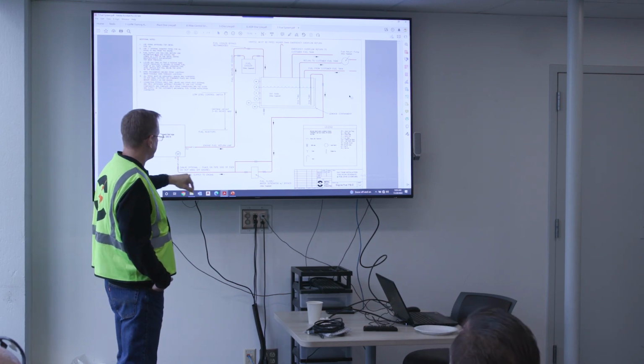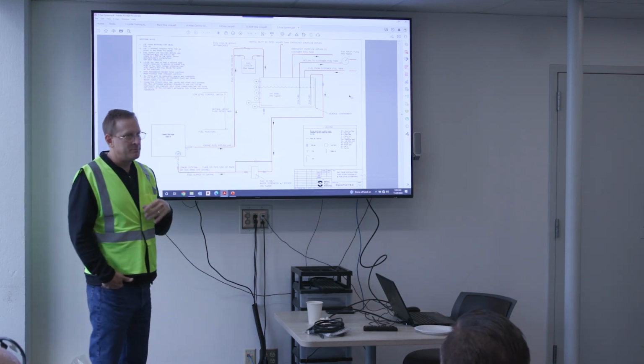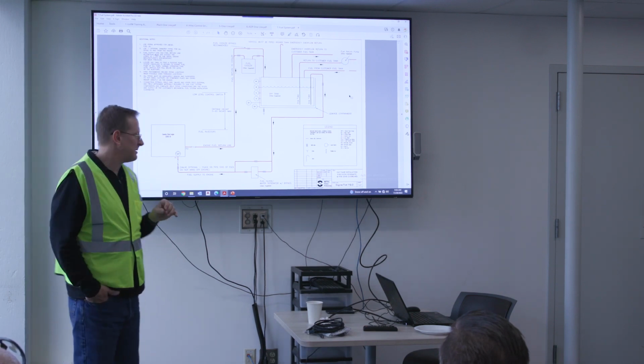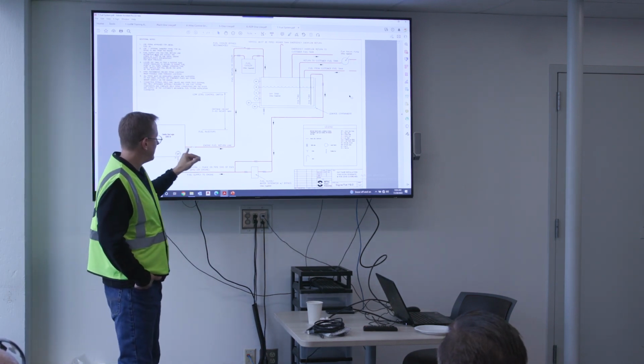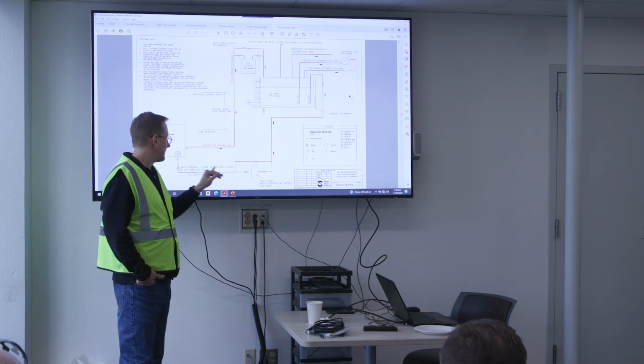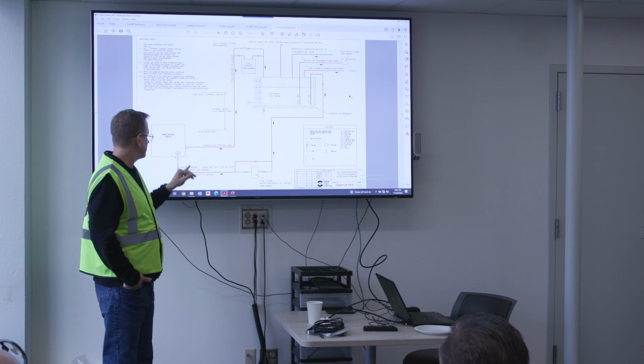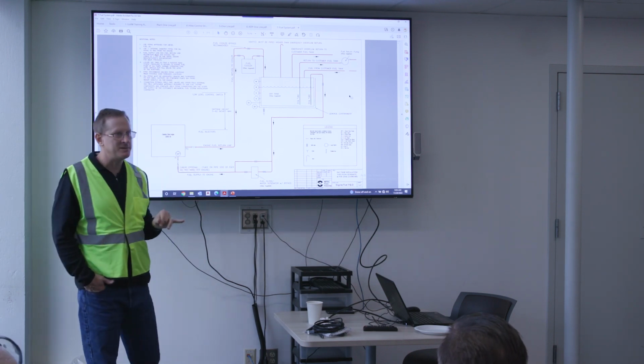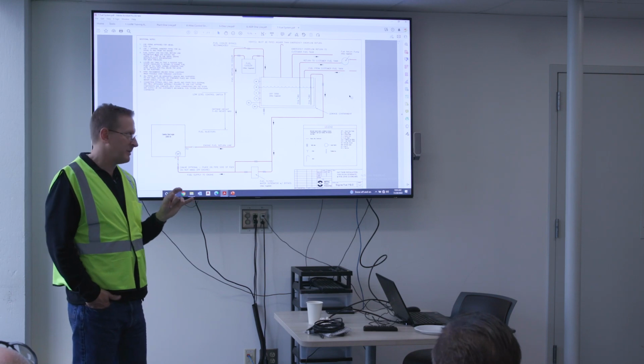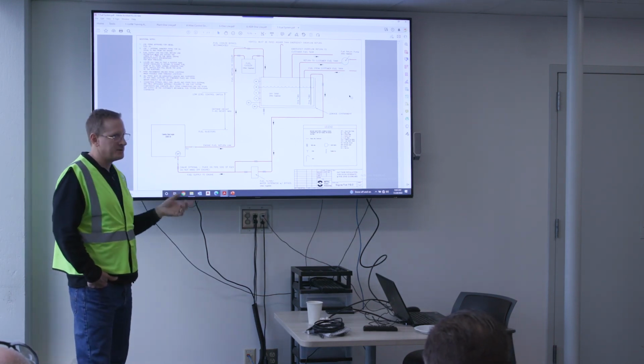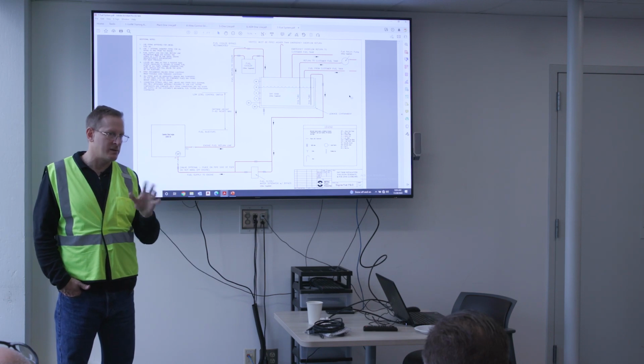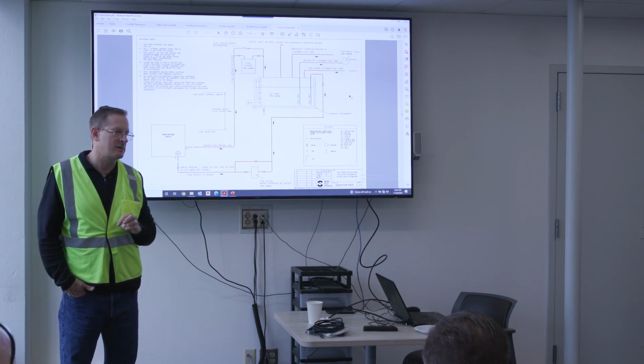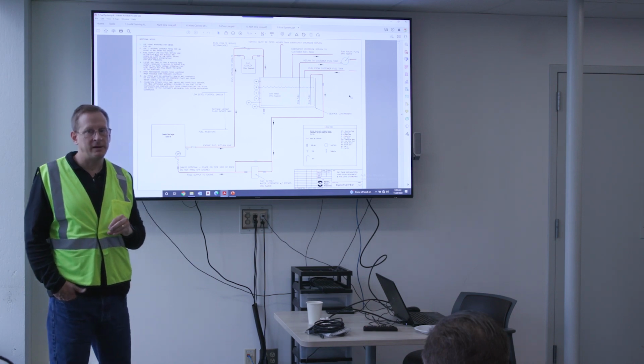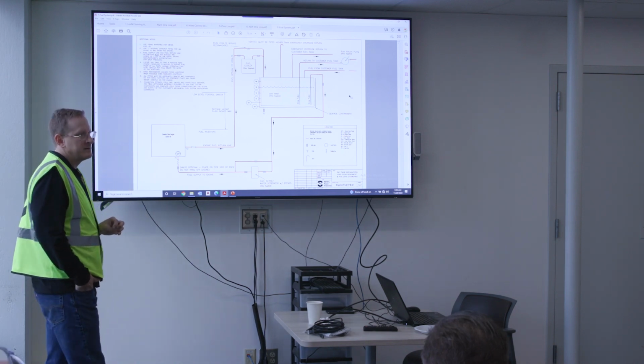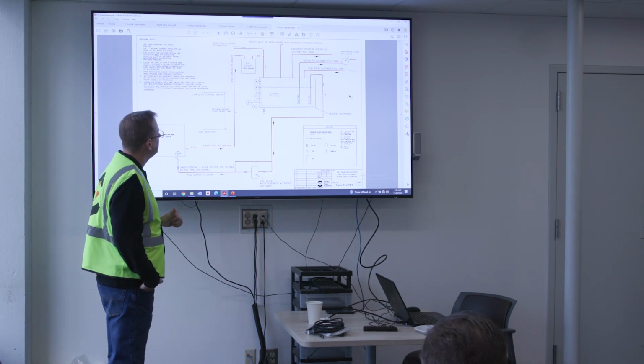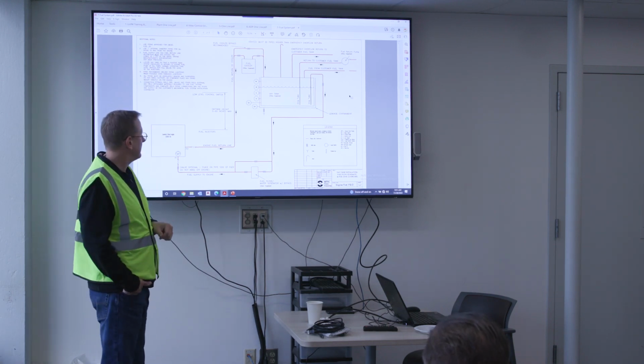We've got isolation valves, obviously, at various places. Make sure that those valves stay open, particularly the ones that are feeding the engine and in the return line. We actually ran the engine at one time with this valve closed, and we blew a line. So it's very important. And what I'd recommend on these isolation valves is that you put little signs on them that would indicate whether they're open or closed, because that's a little confusing at times. Those are all manual? Those are manual valves. Those are hand-turn valves. And I'll point those out to you in the walk around.